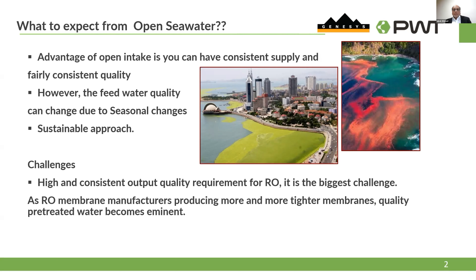As RO manufacturers are producing more and more tighter membranes — for instance, in the late 90s and early 2000s, membrane surface area was about 300 square feet, but now we have membranes at 440 square feet. Thanks to automatic winding machines and consistent glue lining, we can increase the active surface of the RO membrane. But on the other side, with tighter membranes, you need even better pretreatment.